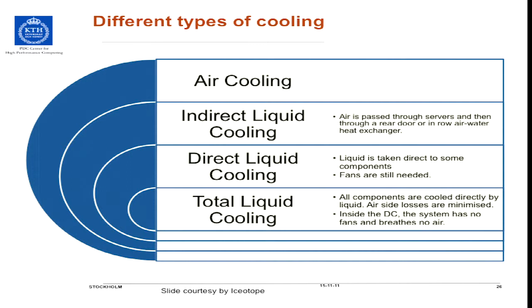I got this slide from Iceotope, a liquid cooling company, the other day, and they have a good classification of different kinds of cooling. There's air cooling, indirect liquid cooling — the hybrid cooling, like the Cray system we have today — and direct liquid cooling, where you actually cool the CPUs directly with water or some other liquid, with pipes out to the actual circuit boards. They also have total liquid cooling, where everything is liquid cooled. In some cases you have 90-95% of the system liquid cooled, but with total liquid cooling, everything should be liquid cooled.